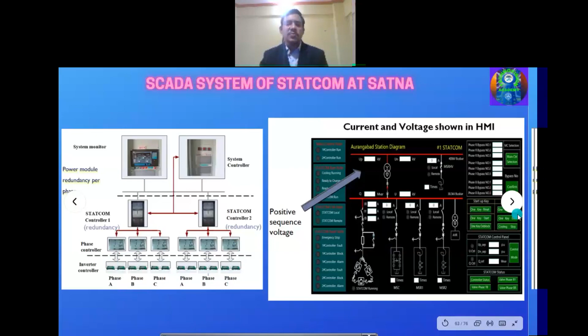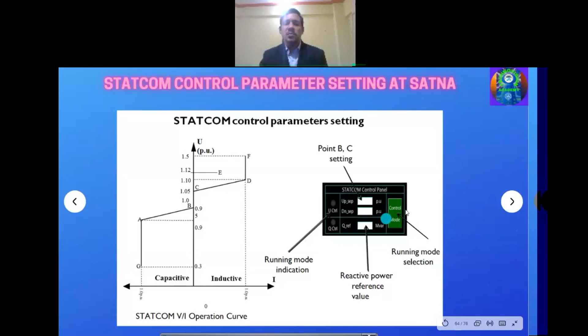Then here, particularly the VI characteristic of the STATCOM, and the STATCOM parameters can be set here. We can feed the parameters from here. We can set the parameters we want in the system, and we can maintain the voltage profile by adjusting this capacitive current or inductive current. It may be from the lowest 0.3 to a maximum of 1.5. We can vary the system voltage this much by using this STATCOM. So this is the benefit of the STATCOM.